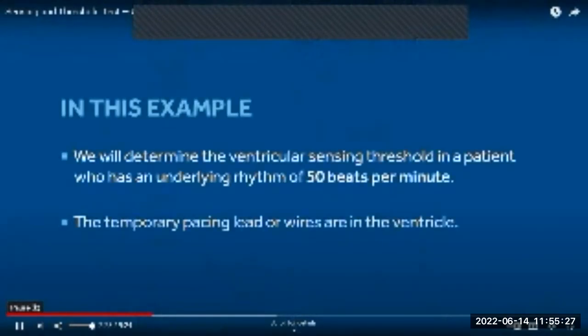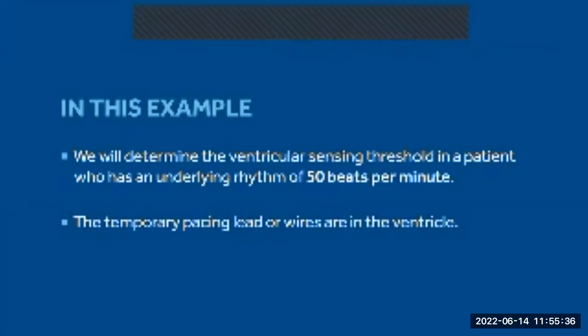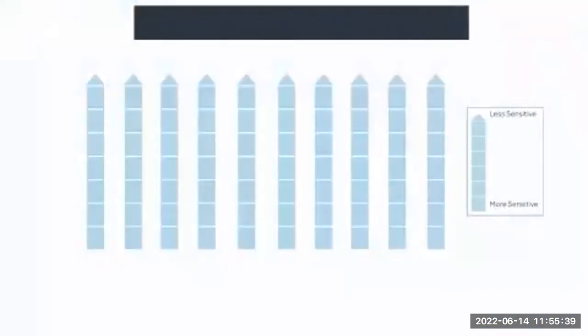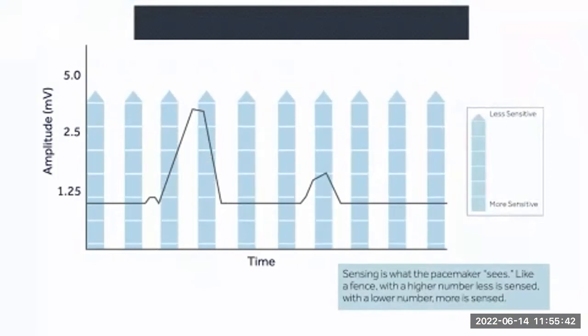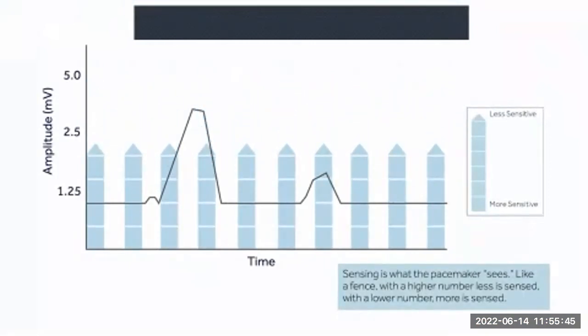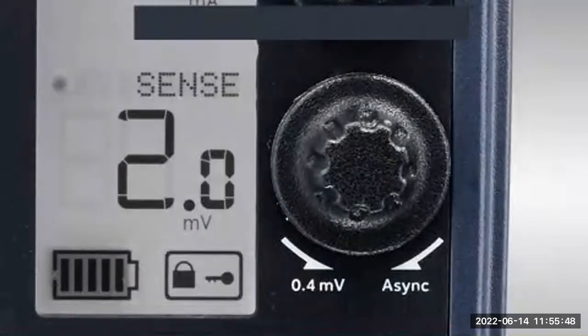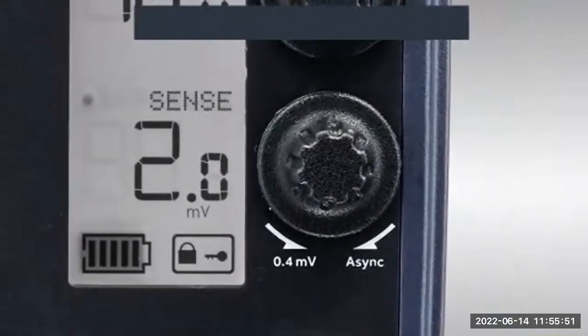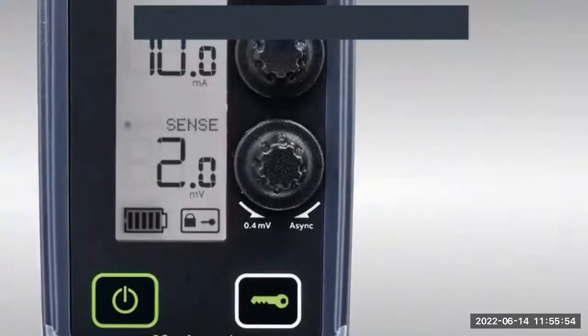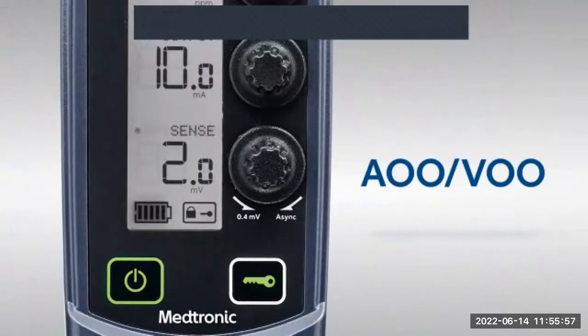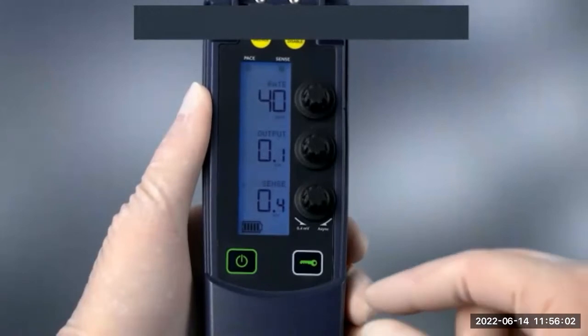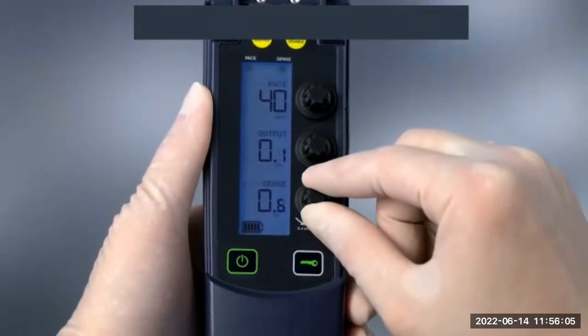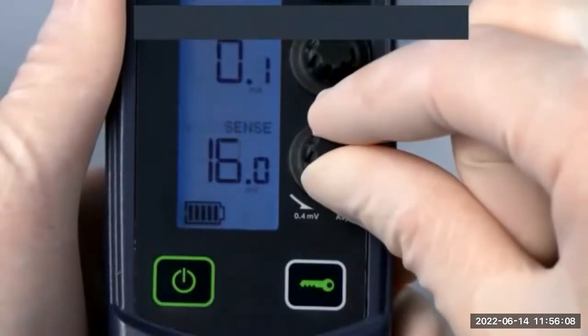In this example, we will determine the ventricular sensing threshold in a patient who has an underlying rhythm of 50 beats per minute. The temporary pacing lead or wires are in the ventricle. Recall the definition of the sensing threshold is the least sensitive setting at which the pacemaker can detect a heartbeat. The sensitivity setting allows you to control the pacing mode between synchronous or demand pacing and asynchronous pacing, also referred to as AOO, VOO. Notice the range on the sensitivity dial goes from the most sensitive setting of 0.4 millivolts to a setting labeled async.